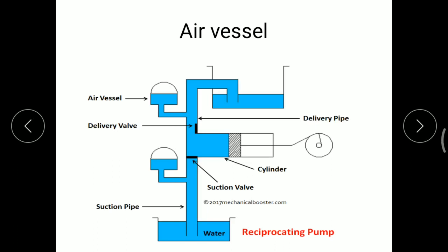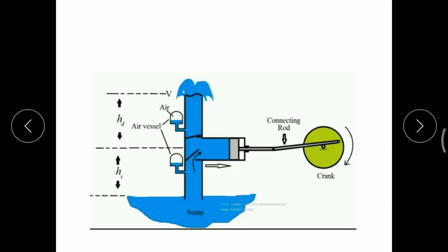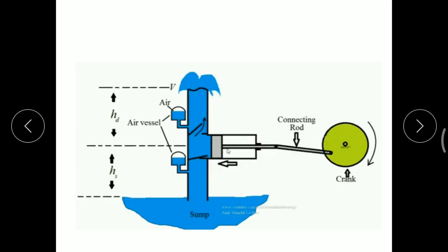Now we will see the working of the air vessel in a reciprocating pump. When the piston moves from top dead center towards bottom dead center, the suction valve gets opened and water comes from the tank towards the cylinder cavity. When the piston moves from bottom dead center towards top dead center, the delivery valve gets opened and high-pressure water flows into the delivery pipe. During the middle of the delivery stroke, when the pump forces water into the delivery pipe at a velocity greater than the average velocity, excess water flows into the air vessel and compresses the trapped air in the upper portion of the chamber.